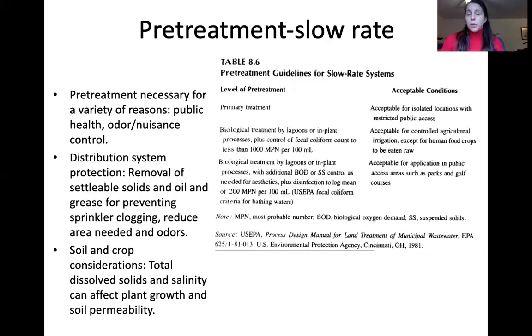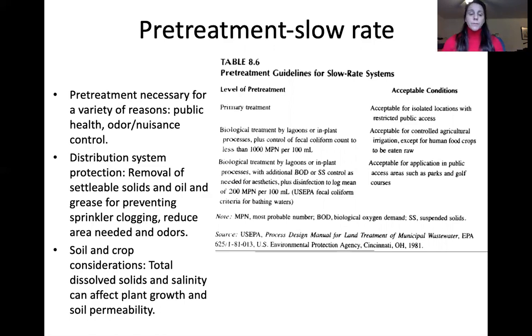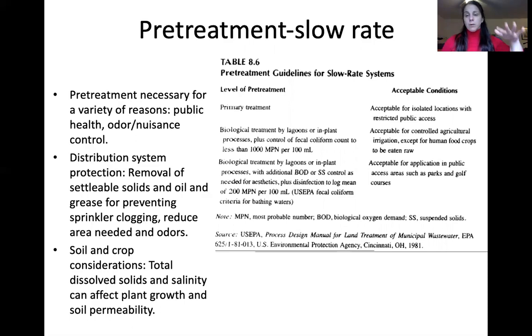Pre-treatment is necessary for slow rate systems for public health — avoiding excessive bacteria — and for odor and nuisance control. It also protects the distribution system: sprinklers can clog with oils and settleable solids. Pre-treatment reduces the land area needed and reduces odors. From a soil and crop standpoint, if total dissolved solids and salinity are too high, it may harm crops and reduce permeability by allowing solids to build up on top.